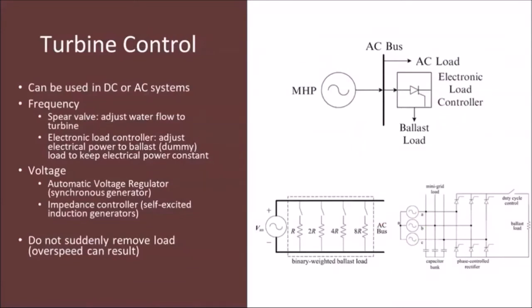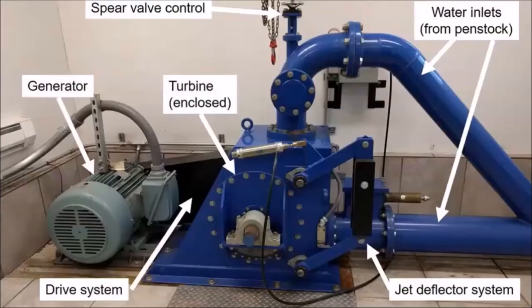A huge advantage of using microhydro is that we can connect directly to an AC load. By diverting just a portion of the river, we can ensure the penstock is always full of water, always supplying mechanical power to the turbine, rotating the generator 24 hours a day. To maintain constant frequency, we can either use a spear valve to adjust the amount of water into the turbine, or use an electronic load controller that balances changes in electrical load with power to a resistive load. Here you can see a multi-jet Pelton turbine installation with water coming from penstocks, a spear valve, and the generator coupled to the turbine through a drive system.